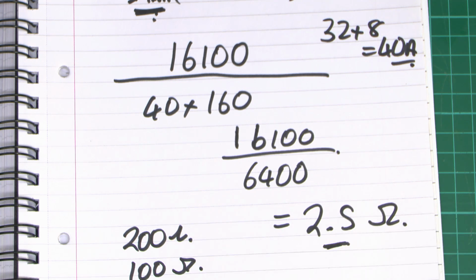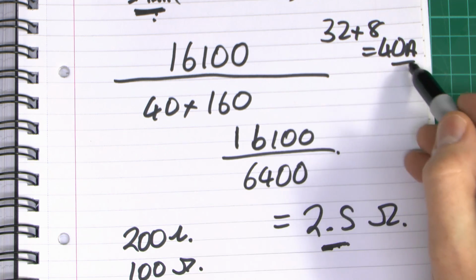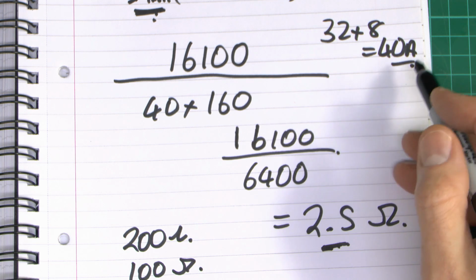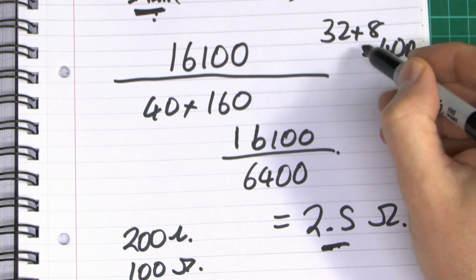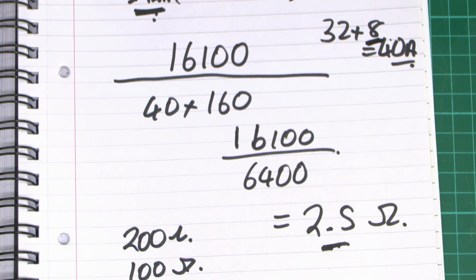So shoving in a rod and connecting it to the existing TNCS earth is not going to be realistic, because you simply won't be able to get it down to this kind of level. And bearing in mind that was only with a total load for the whole installation and the vehicle of 40 amps, which gave us that rather unlikely 8 amp load for the rest of the property. So it's just turning on a washing machine or tumble dryer, and you're going to be above the 8 amps there.